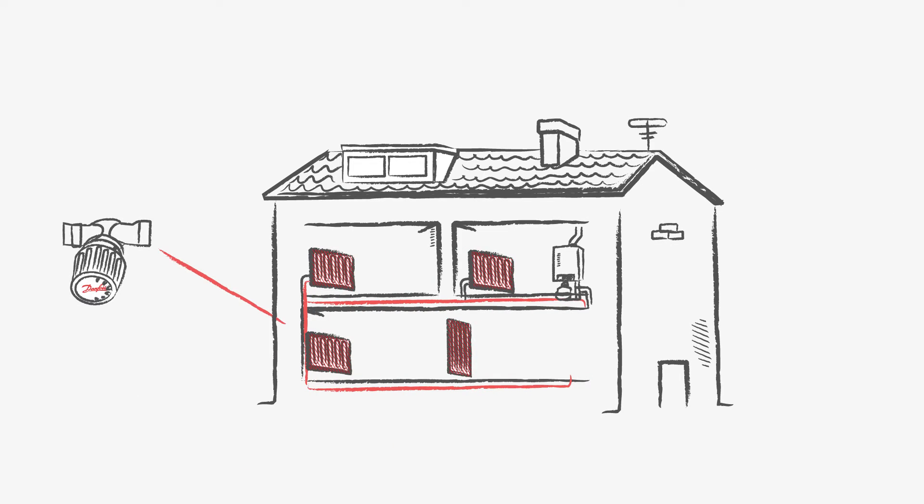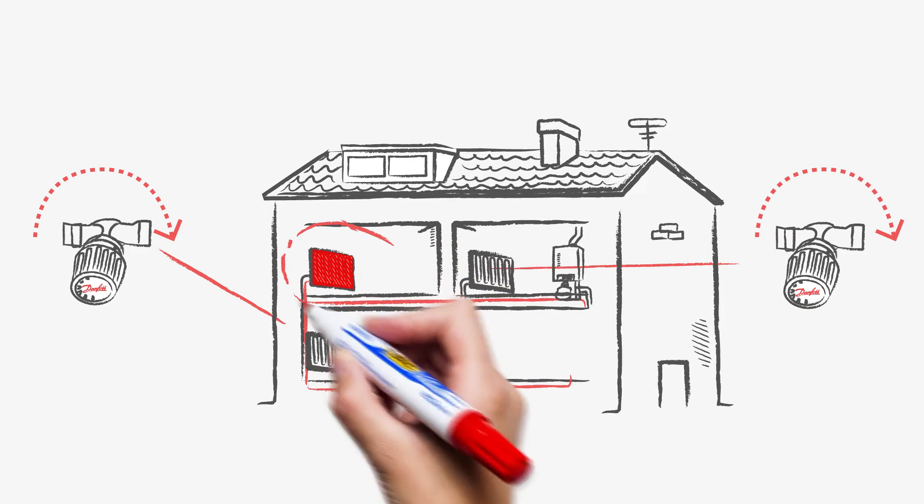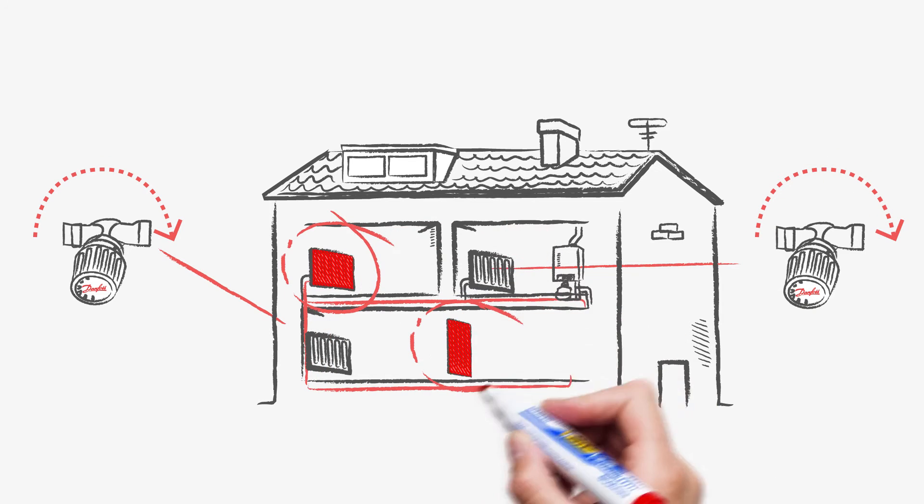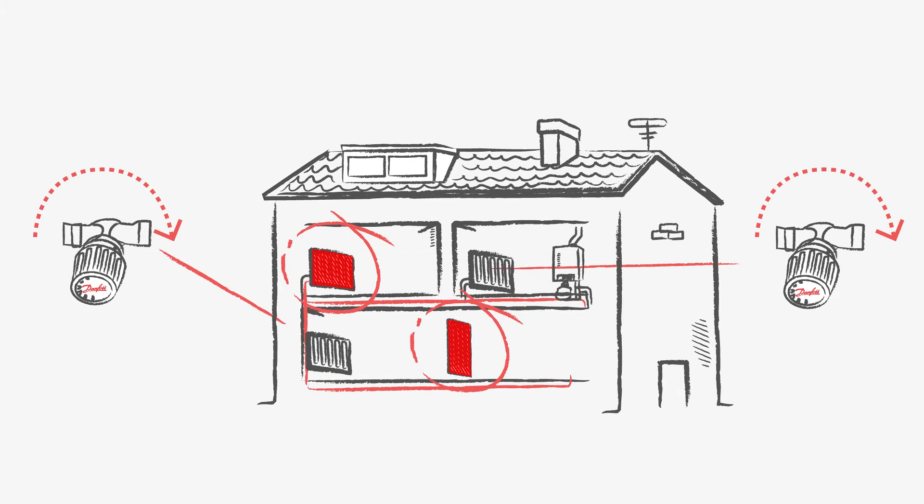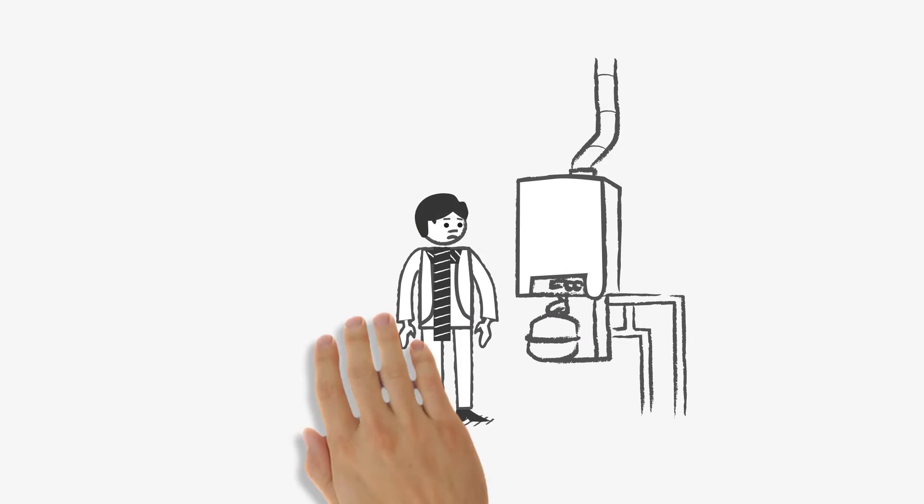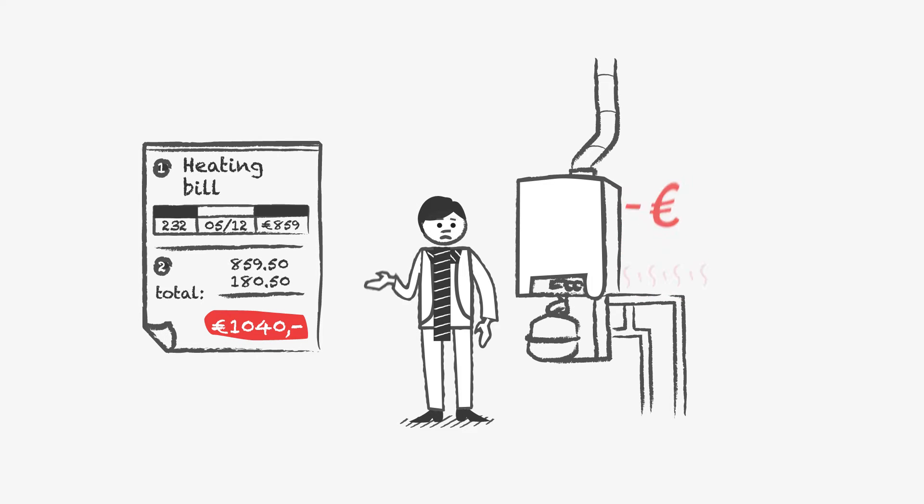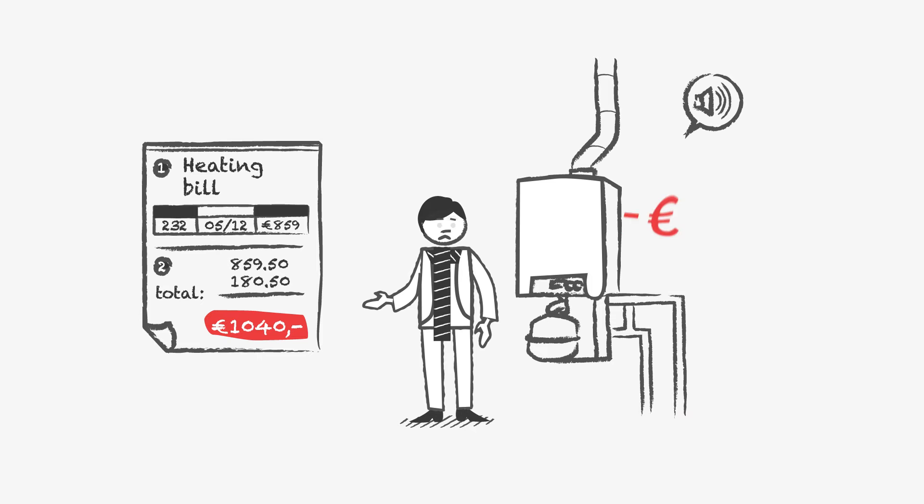When several radiator valves are closed, the water distribution changes, allowing even more water to flow through the other radiators. These overflow conditions result in significantly decreased energy efficiency of the heating boiler, unwanted heat losses, and sometimes troublesome rushing sounds.